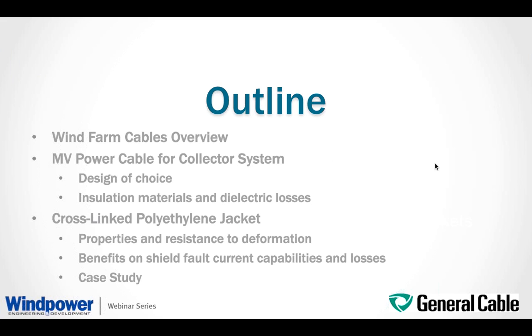First, I'll give a brief overview of the various cable constructions used on a typical wind farm. We'll then review the design features of choice for the medium voltage power cable used for the collector system. Then we'll talk about the different insulation materials and their characteristics and how they influence the dielectric losses. Finally, we'll talk about the benefits of using cross-linked polyethylene as a jacket, and how its enhanced resistance to deformation allows further optimization of the concentric neutral sizes, which will provide better efficiency over the life of the cable and lower line loss.